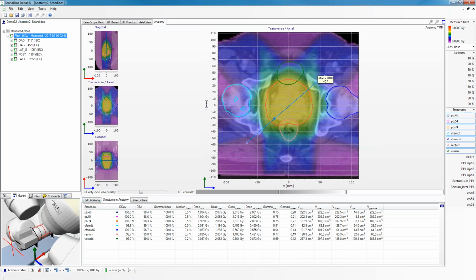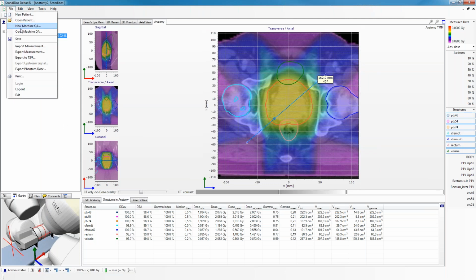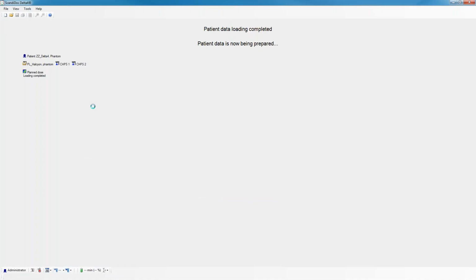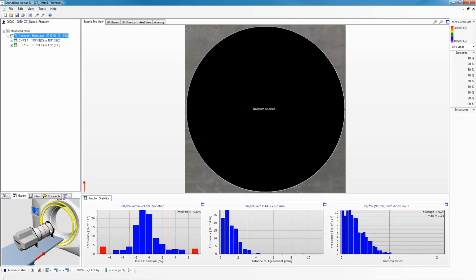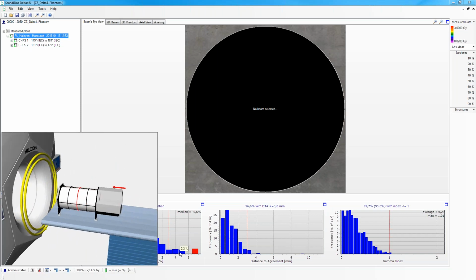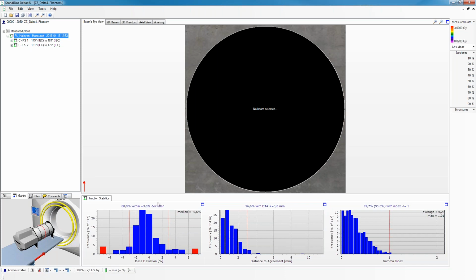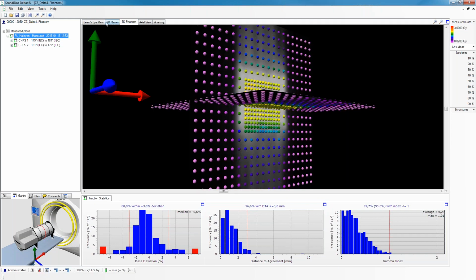I thought I'd just quickly show you: this plan is measured on a regular linac. I can see this by looking at the graphics here underneath the patient information. It was measured with a Varian TrueBeam. Just to show you how similar everything looks when I'm looking at data measured by a different machine, I'm just going to open this Halcyon plan, and you can see that now this is a measurement done on a Halcyon machine, but the display is identical. So I still have my fraction statistics where I have my dose deviation, distance to agreement, and gamma. I can look at the data in all of the different views, and it looks the same.